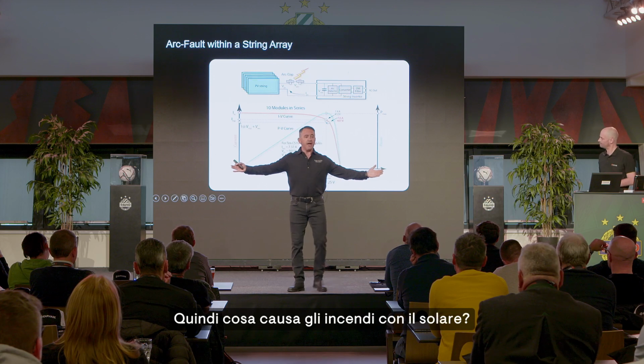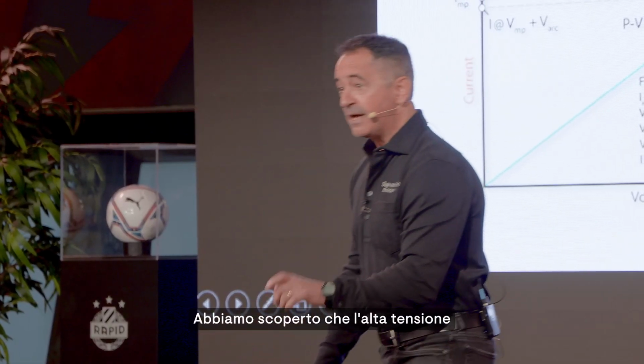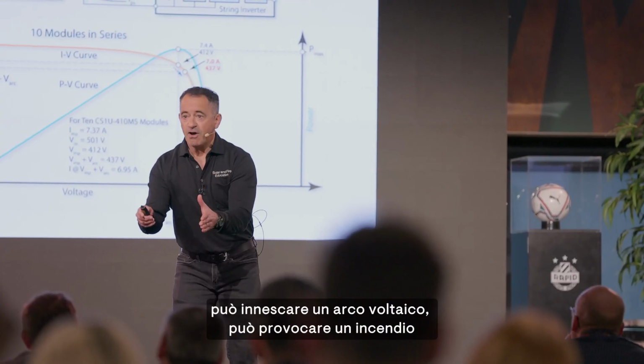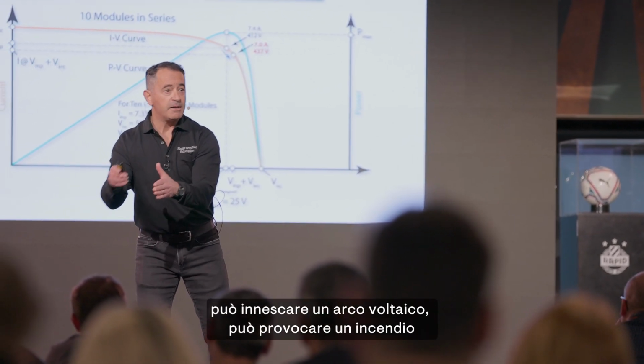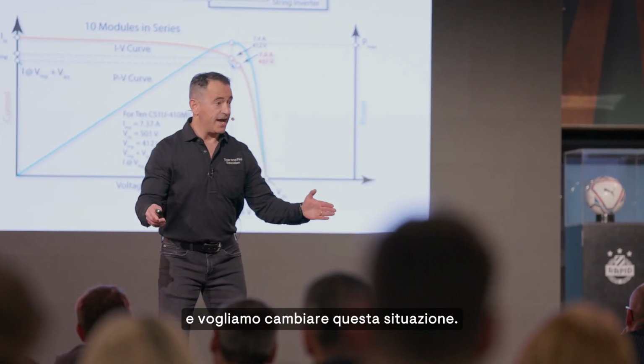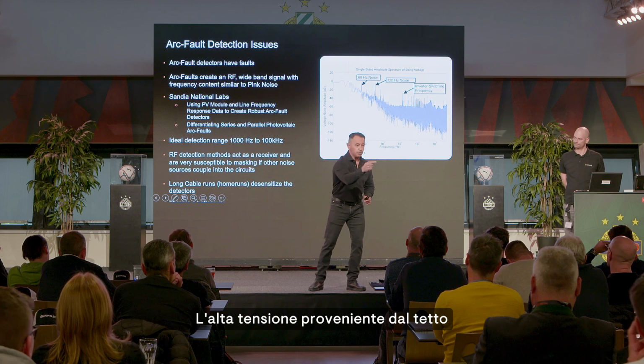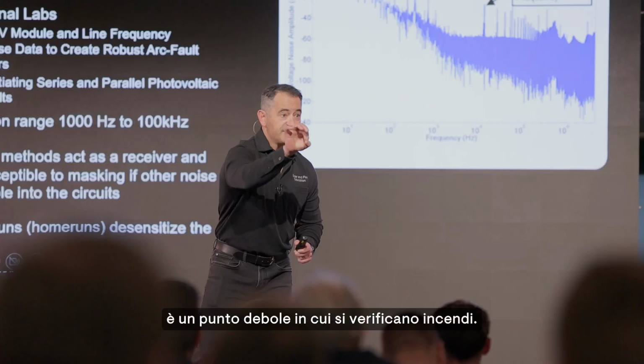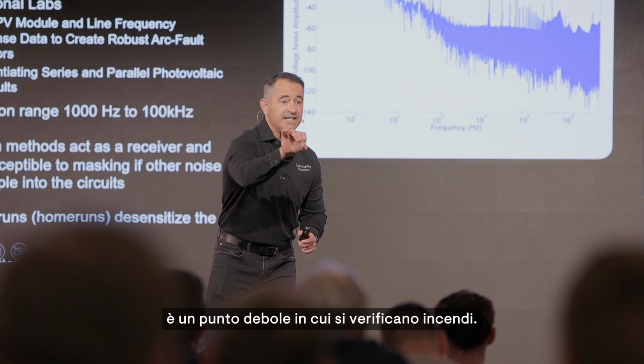So what's causing fires with solar? What we found is that high voltage can start an arc, can start a fire, and we want to change that. That high voltage coming from the roof, connecting to an inverter, is a weak point where we see fires starting.